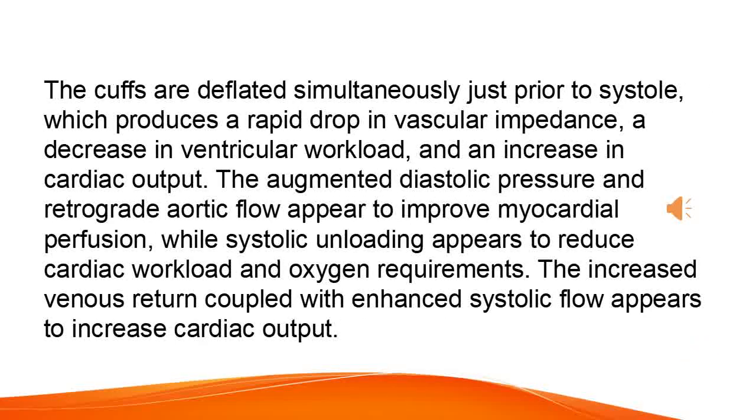The cuffs are deflated simultaneously just prior to systole, which produces a rapid drop in vascular impedance, a decrease in ventricular workload, and an increase in cardiac output. The augmented diastolic pressure and retrograde aortic flow appear to improve myocardial perfusion, while systolic unloading appears to reduce cardiac workload and oxygen requirements. The increased venous return coupled with enhanced systolic flow appears to increase cardiac output.